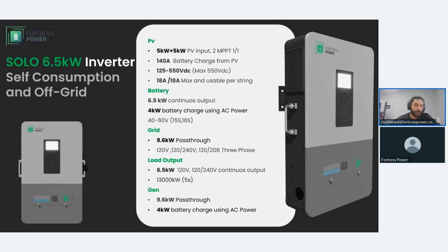For the grid, you have a 9.6 kilowatt pass-through. Okay, so pass-through from grid input to load. And then this inverter can do 120/240 split phase, or 120 single phase. And then it can also do 120/208, having a minimum of 3 inverters, okay? Where we can parallel up to 6 inverters of the Solo 6.5. That's the maximum scalability.